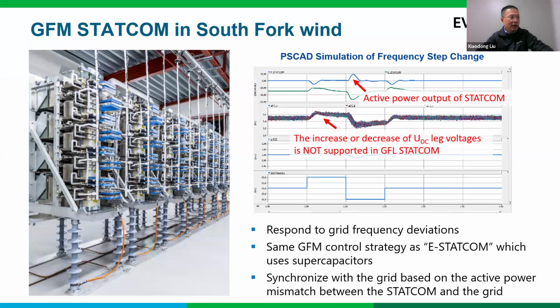We know that some manufacturers have developed a so-called enhanced STATCOM since I think 2021. And the enhanced STATCOM uses supercapacitors to store much more energy and achieve a much better performance. Based on some studies, the enhanced STATCOM can provide inherent inertia which is 10 times larger than the same size of condenser. That's a really amazing technology advancement. The grid-forming STATCOM in South Fork Wind had the same control as the enhanced STATCOM, but a little bit reduced frequency supporting capability, but it's still good. So with the grid-forming STATCOM in operation in South Fork Wind, Eversource has been starting to explore potential application of enhanced STATCOM in the Eversource system.